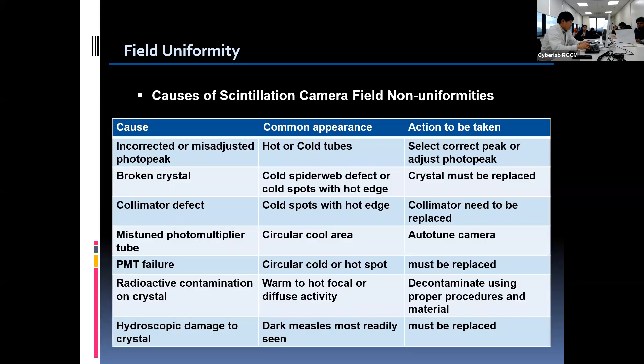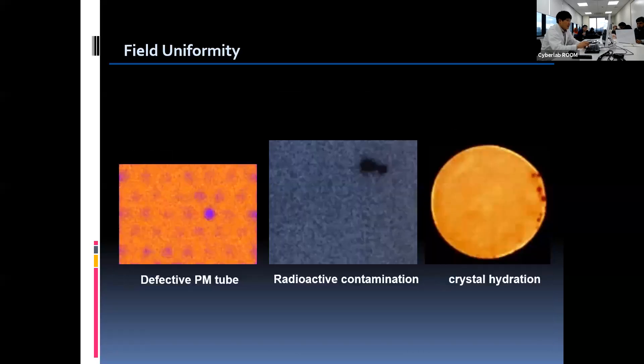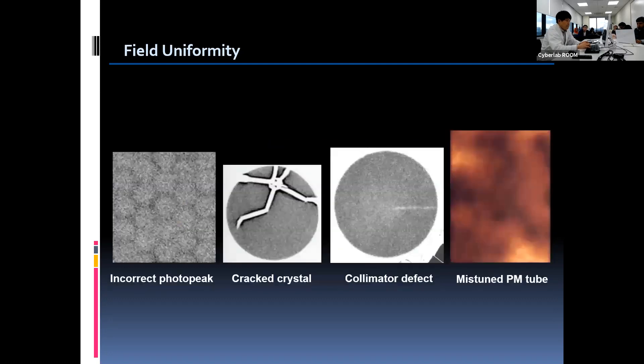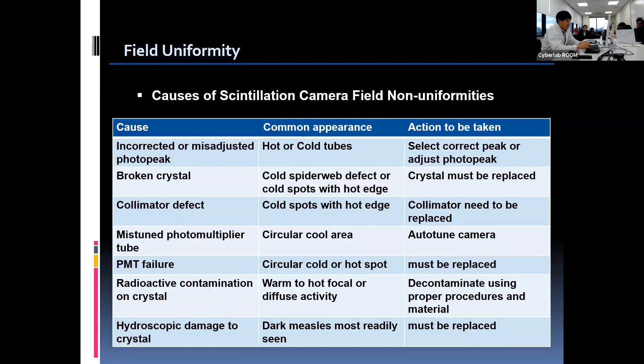And lastly, hygroscopic damage to the crystal can show dark images. In this case, the detector crystal must be replaced.